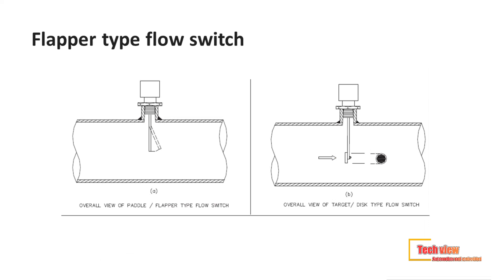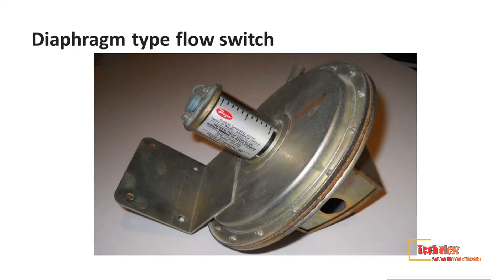When the flow is generated in the process line, the force will act at the flapper and swing it away. This causes the magnet's position to change in relation to the reed contact, triggering the contact.